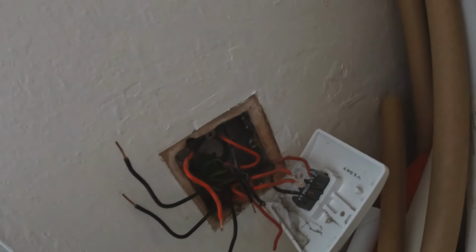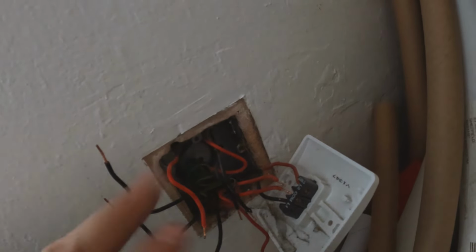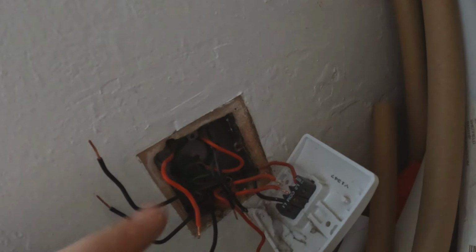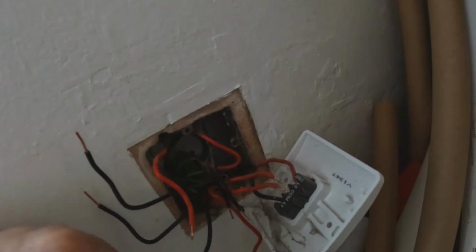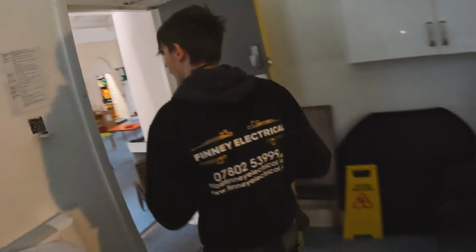Ellis just told me the fuse board's gone clear, which means if that's the case, and this is the only switch open, we can cap all these off, turn it on, find out which is the feed in, turn it off again. All the clear ones we can bang together, all the bad ones we can leave out. We'll turn it on again, see what turns on. Anything that is off, then we need to look into. So that's what we'll do. Let's check this fuse board being clear now.